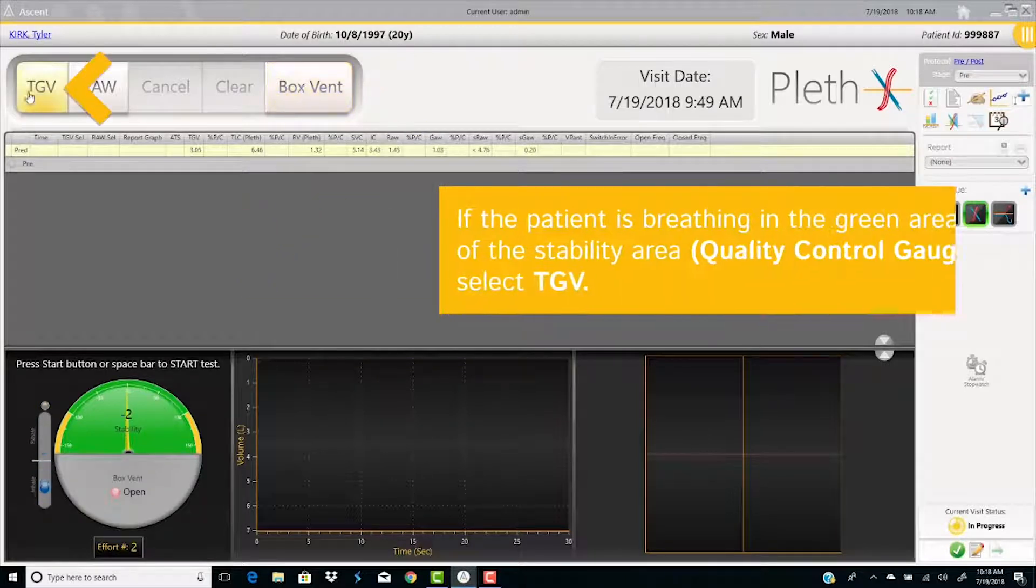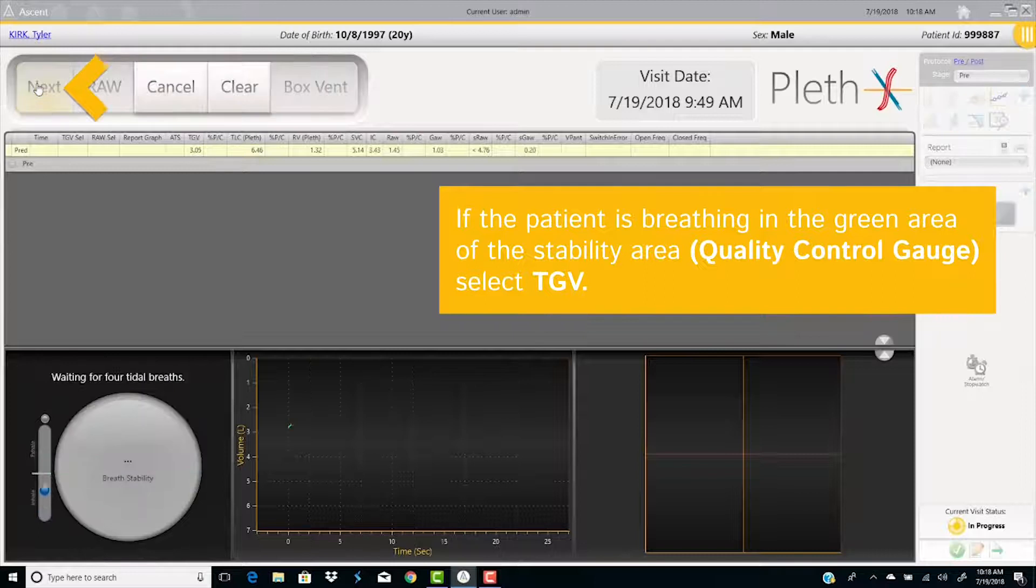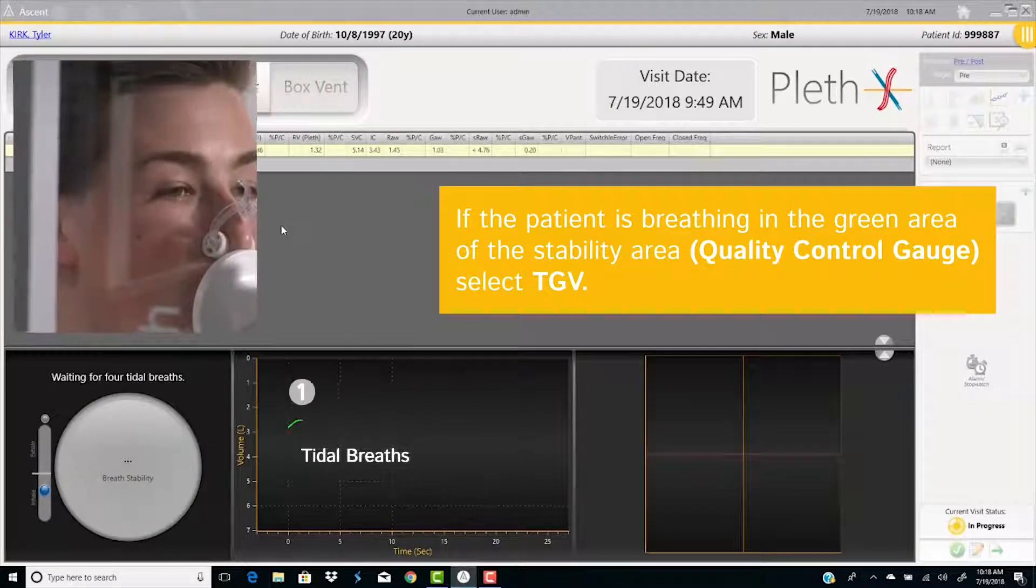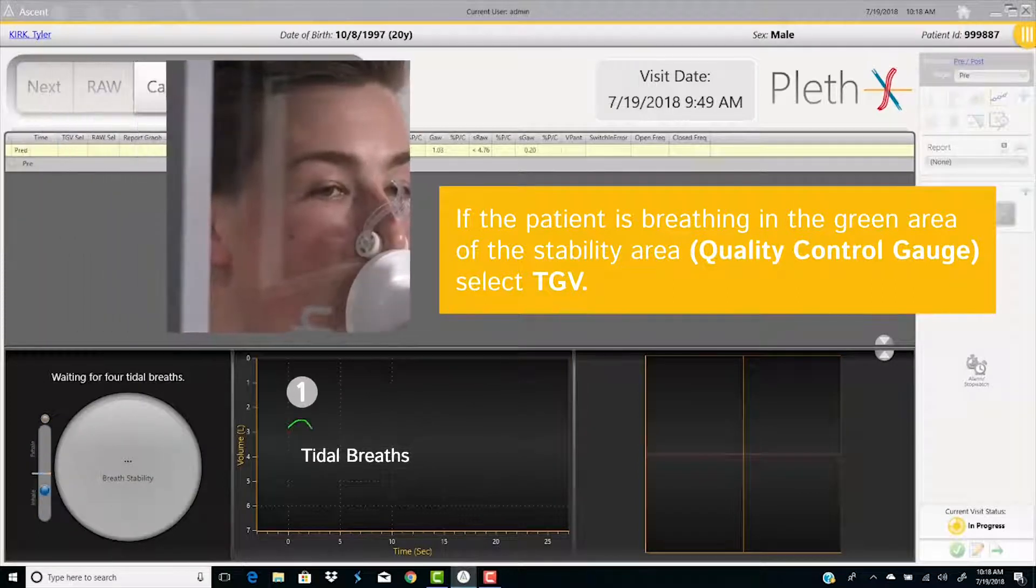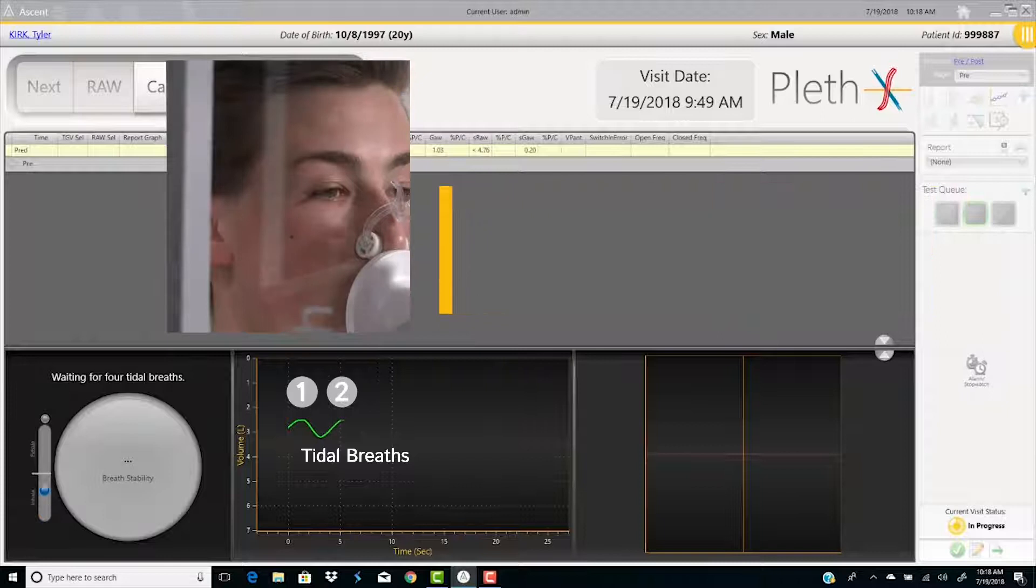If the patient is breathing in the green area of the stability area, the quality control gauge, select TGV. Collect at least four stable tidal breaths.